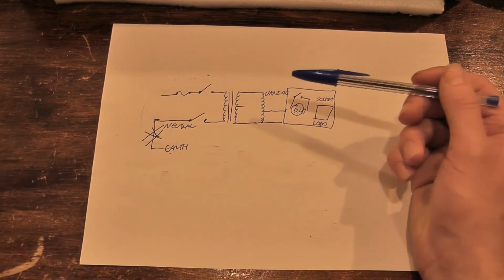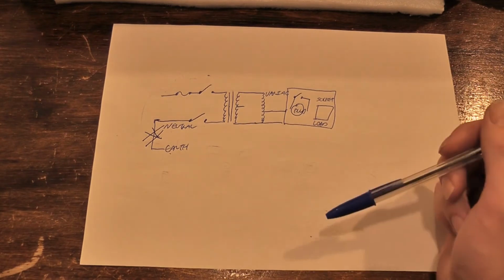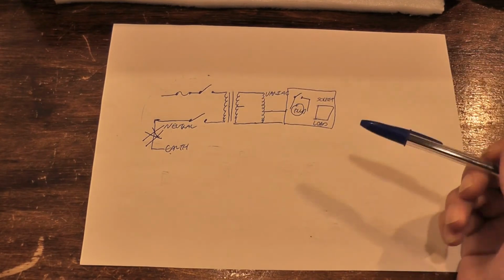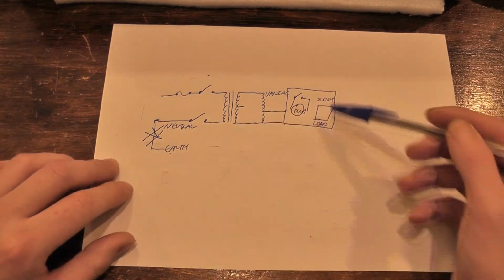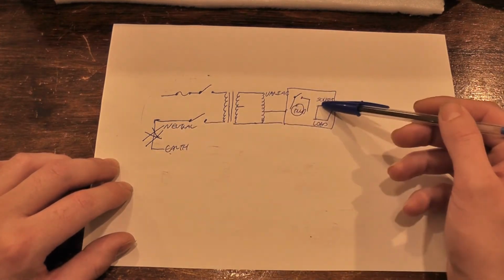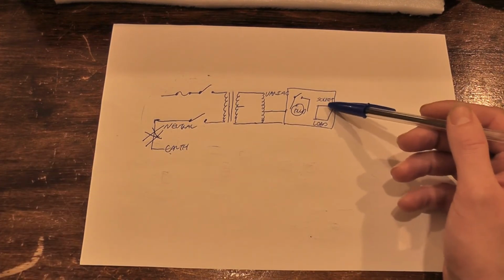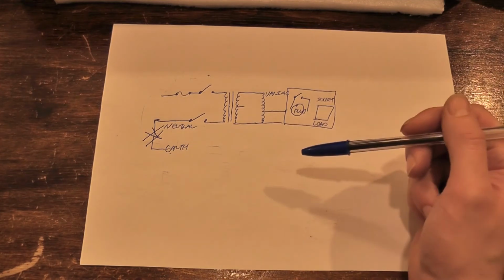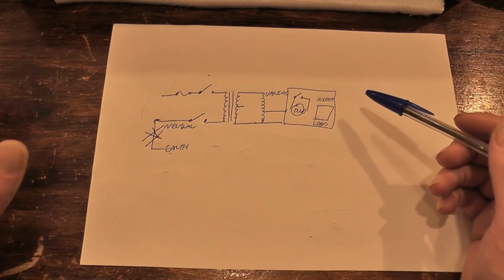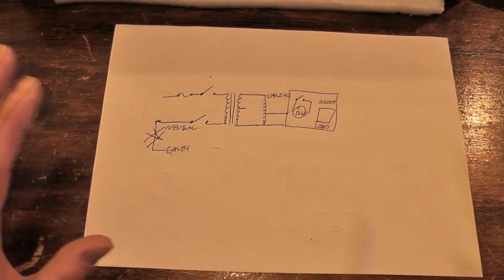There are some instances where you might want a center tap transformer and actually connect earth to it. I know that sounds a bit weird because you can now get a shock off either one of these two wires, but there are reasons you might want to do that. The general way would be just to connect earth straight to this socket, so your appliances are still referenced to mains earth. But then again, there are some instances where you wouldn't want that and you want it fully floating.